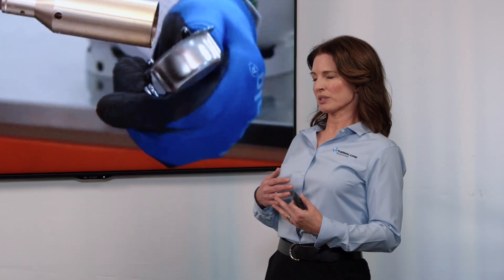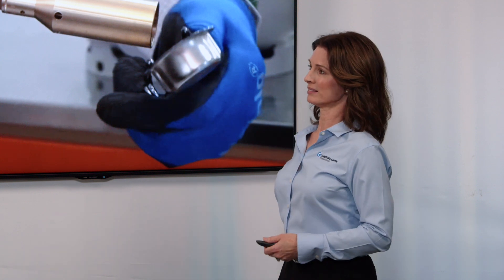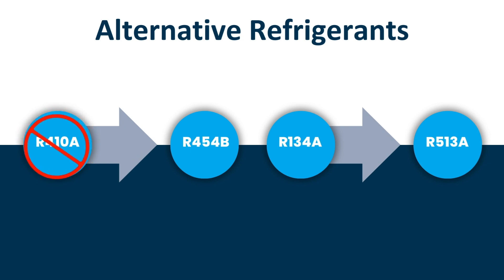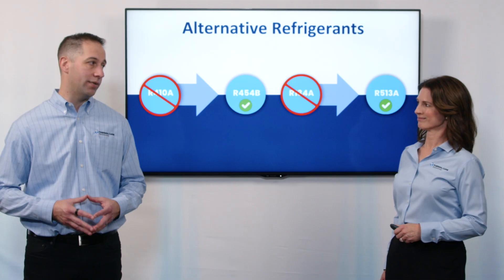Do us a favor, Mike — go back in history a little bit and tell us how Thermal Care got to this point. How did you plan ahead? We saw the writing on the wall and we knew these regulations were coming. We knew we had to make the best choice for our customers and for our products. What we decided to do was take all of our R410A products and transition them to R454B, and take all of our R134A products and transition them to R513A. To do this, we had to change our compressors, our evaporators, and even a couple of suppliers. But if we hadn't put in all that work ahead of time, we would not have been ready to ship products into those 12 states at the beginning of 2024.